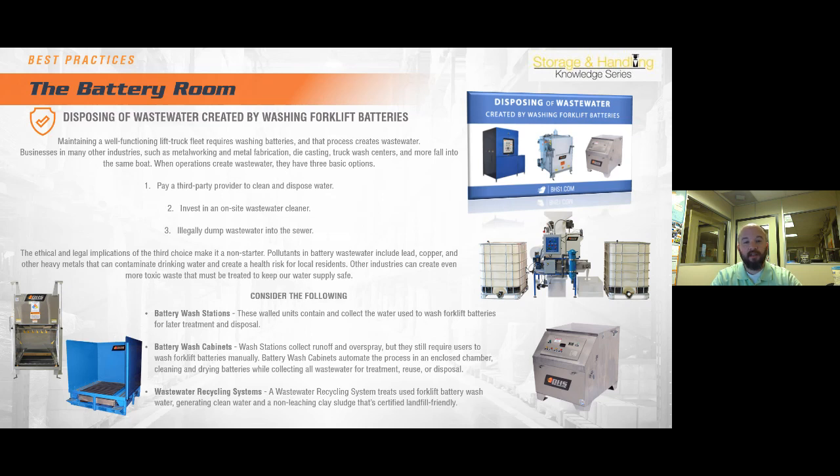There are a few different solutions as far as washing them, but also dealing with the water, which we'll cover first. The water that is used to wash batteries technically becomes a hazardous waste at that point, because as that battery gives off the water that's in it, it's going to contain lead and acid, which is not good for humans as well as for dumping down the drains. So one solution is to have a recirculation unit which stores that water and filters it, allowing for use typically between 6 to 12 months before it needs to be disposed of by a wastewater company that can properly take that water out and dispose of it.